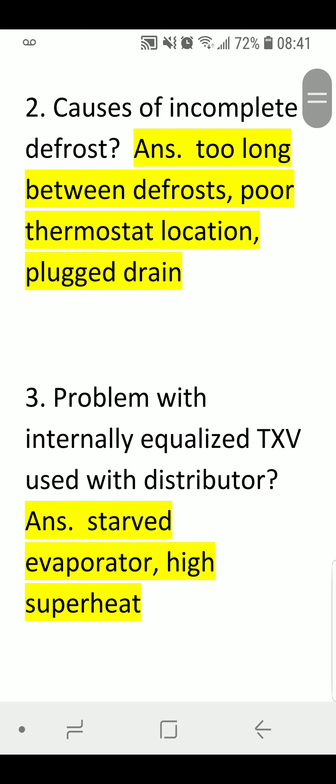Causes of Incomplete Defrost. Answer: Too long between defrost, poor thermostat location, and plugged drain.